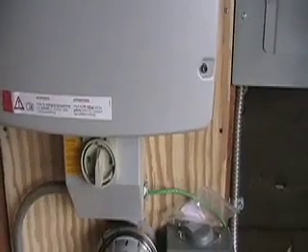I'm tapping off this breaker, this subpanel here, and it's a back-fed breaker because the solar system will first power the garage and then the rest of the house. Service can never exceed its rated capacity because the solar system, at most, is going to produce the same energy that will be needed by the garage — it'll never draw more than its rated capacity. And this is the inverter, a 7 kilowatt Sunny Boy inverter, one of the best on the market, with an enclosed and attached disconnect.